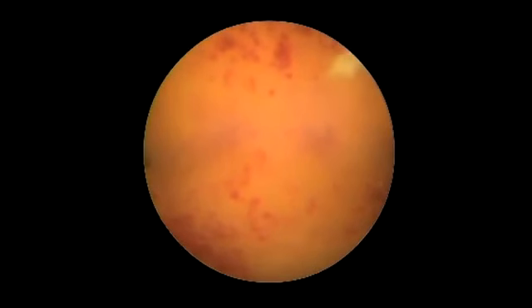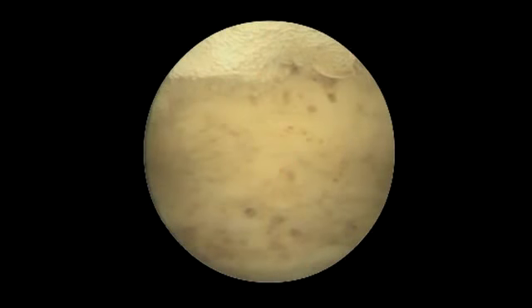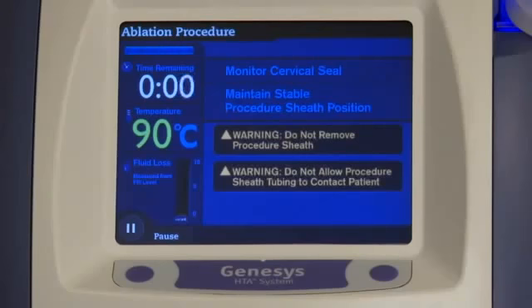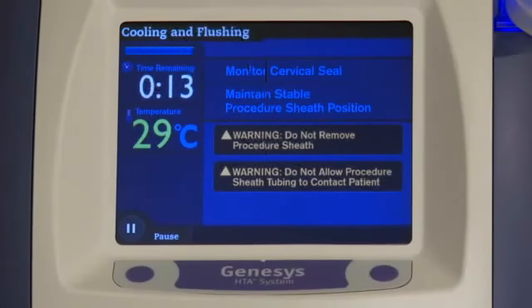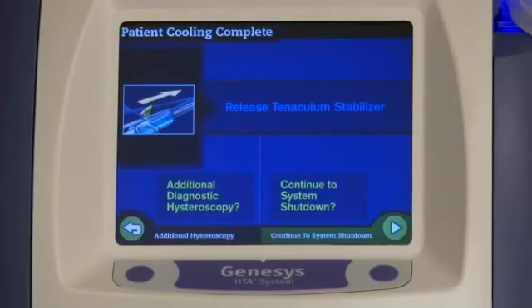The Genesys HTA system allows for viewing of the entire ablation from start to finish. As shown in this time-lapse sequence, the pink cavity blanches white as the procedure advances. When ablation is complete, the system automatically begins flushing the uterus with room temperature saline for 90 seconds. Do not remove the sheath until the cool-down process is complete. A chime will indicate that cooling and flushing is complete and that the fluid temperature is less than 45 degrees centigrade.